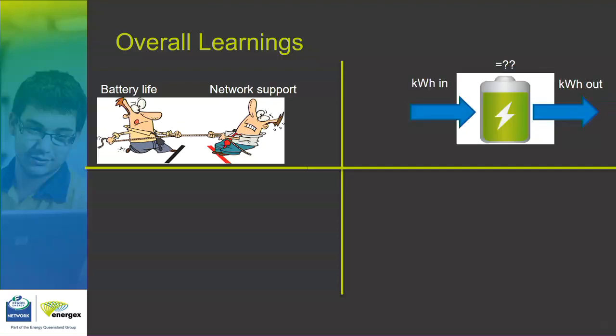Kilowatts in does not equal kilowatts out. What I'm saying is I can support a network and discharge the energy, but I need to get that same amount of energy back into my battery again. On a weak network, where I might be injecting energy for 10 hours a day, I've then got to get all that exported energy back in again. How do we make sure we're topping our batteries back up and we don't end up with a case we always seem to get on our network with some of our batteries?